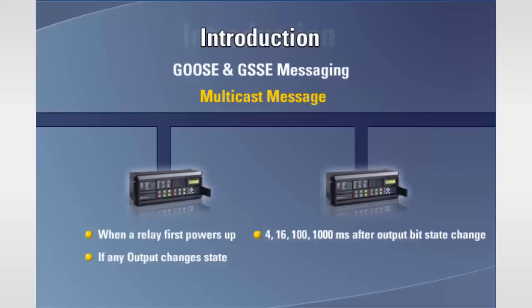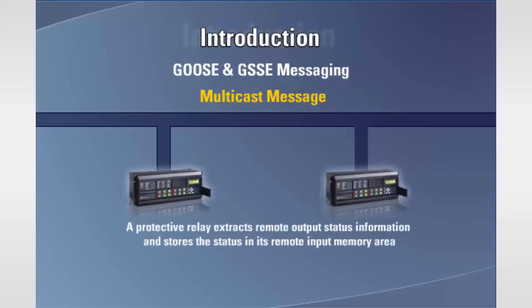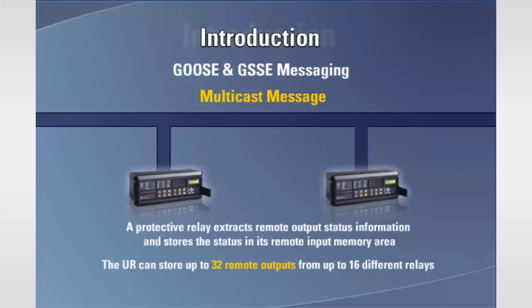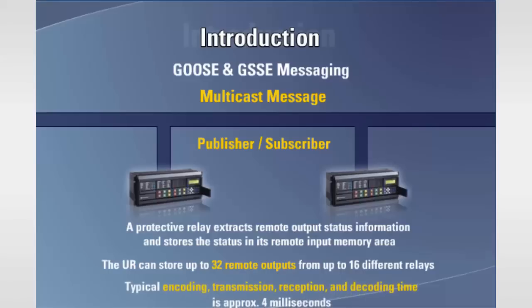Multicast messages are also broadcast on a user configurable periodic basis, which can be set for once every 1 to 60 seconds. A protective relay interested in remote output information from another relay will extract the appropriate remote output status information and store the status in its remote input memory area. The universal relays can store the status of up to 32 remote outputs from up to 16 different relays within local remote input status tables. This method of data exchange has sometimes been referred to as publisher-subscriber. The typical time taken for the encoding, transmission, reception, and decoding of a GSSE or GOOSE message between universal relays is typically in the quarter cycle time frame, or approximately 4 milliseconds.